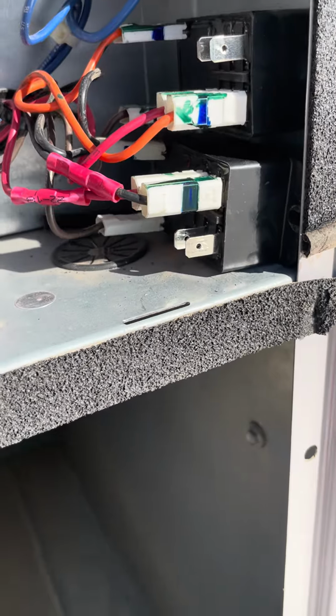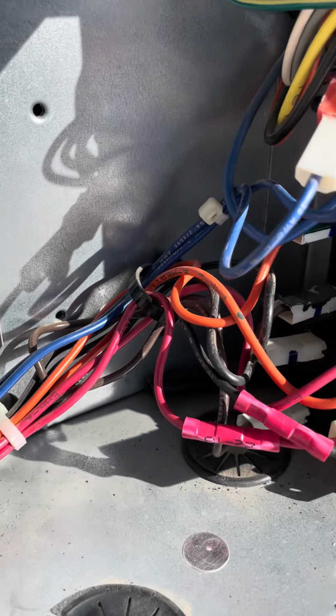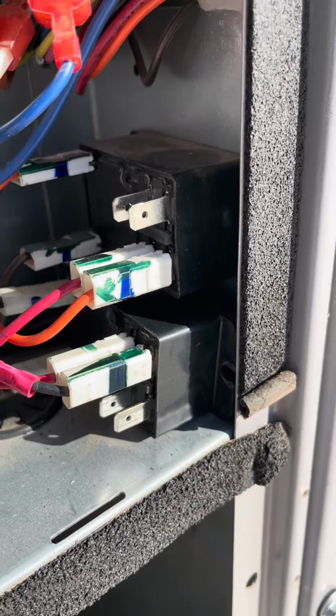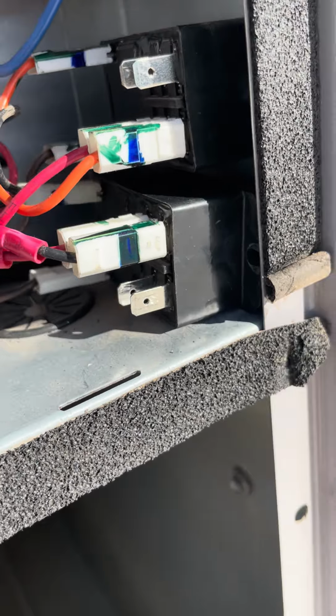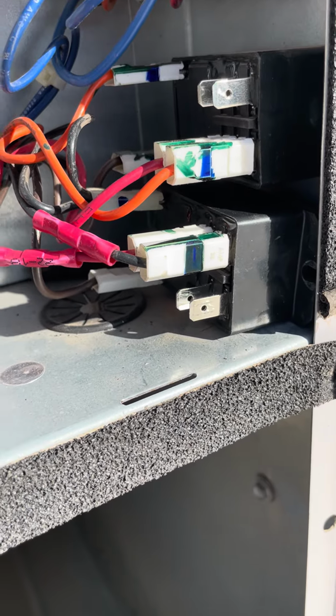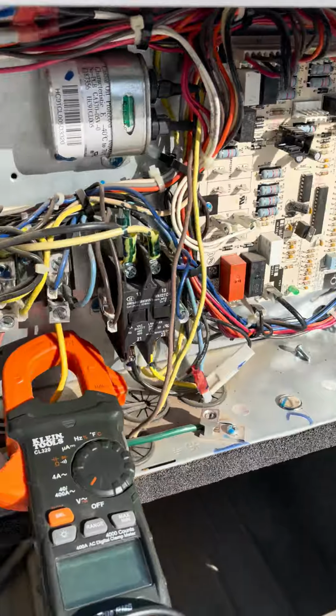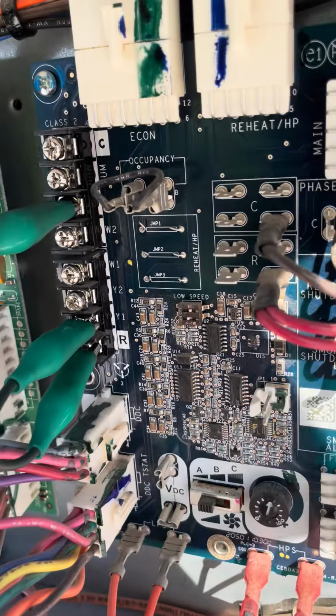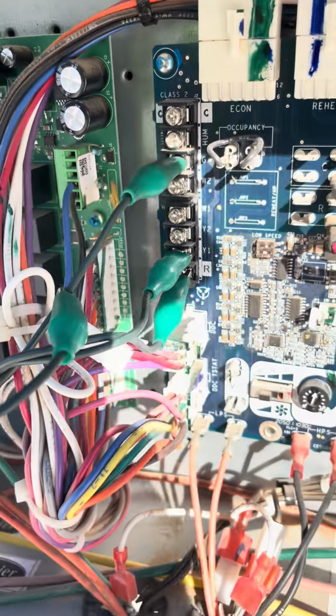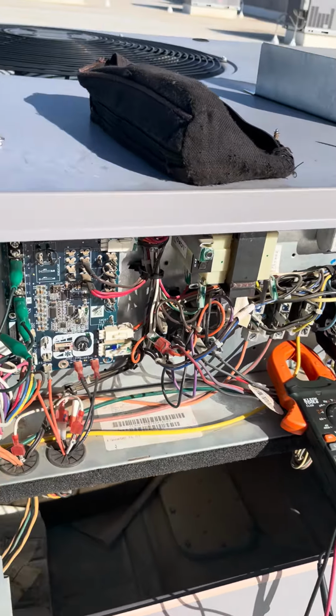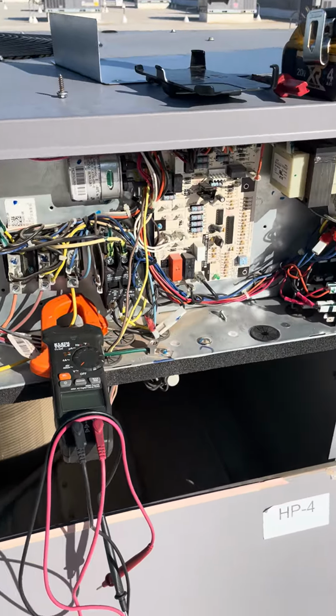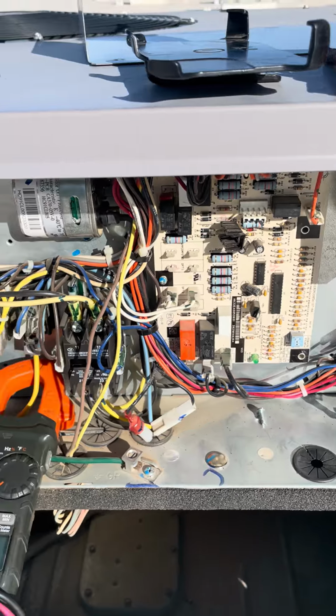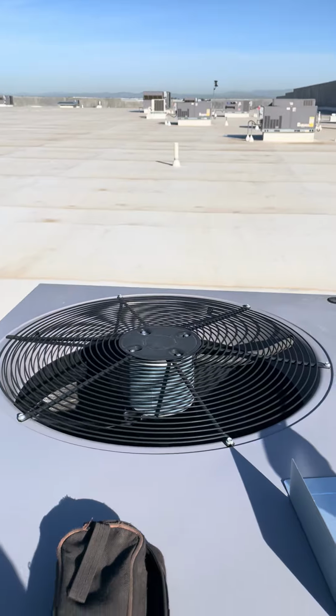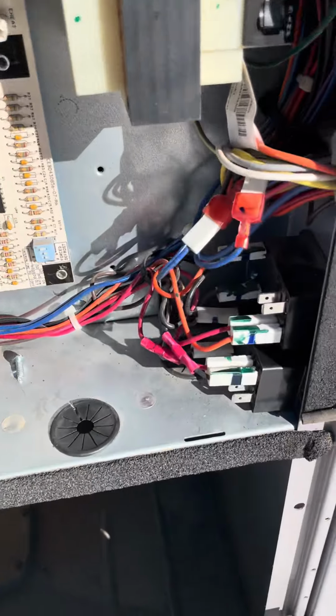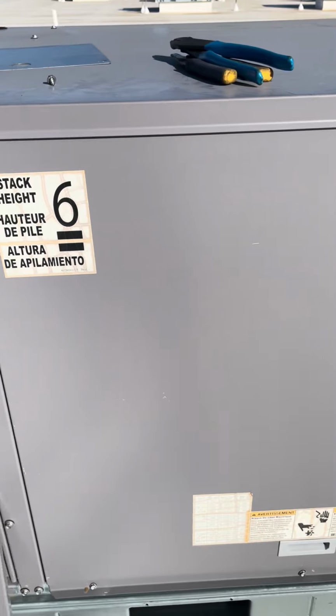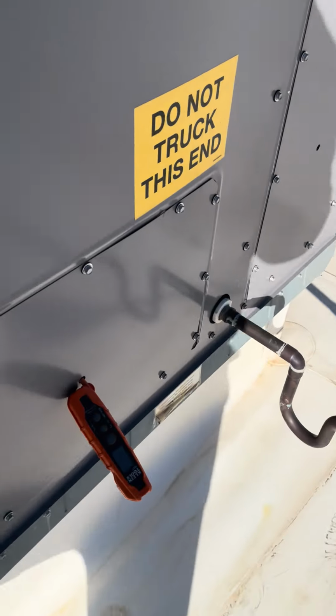All I did, there's two different sections of this relay. There's top contacts and bottom contacts. The bottom one is where the wires were. I just removed them and put them on the top one to test it so you can see what's going on. We're still jumping for cooling. So now we're just going to energize the unit again. Sequence of operation. Fan came on. So it's running again, same wiring and everything.